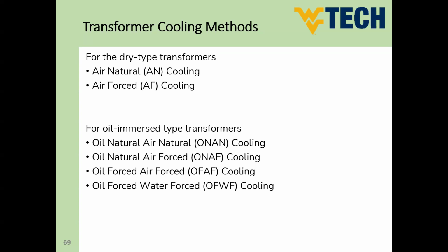You know, it's possible to have some other devices without cooling systems if it's going to be turned off for a while in order to evacuate the accumulated heat inside. So this is possible. However, this has to be designed and considered in the design phase of any project. So now, for our devices like the transformer, it's going to work 24/7. So no way to operate these devices without a cooling system. So you have to have a cooling system. So what are the types of cooling systems? This is what we are going to discuss in this part right now.